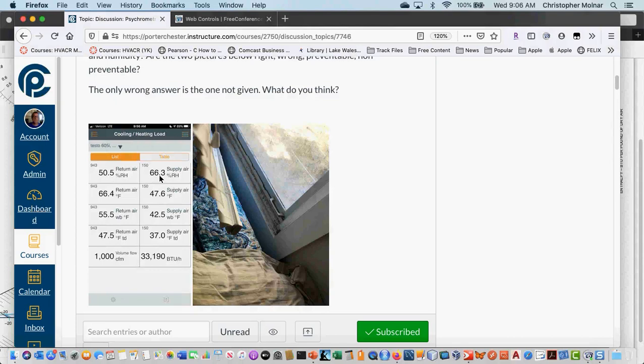I have a 66.3 relative humidity supply air. We talked about this yesterday, that the supply air can and should have a slightly higher relative humidity, but remember it has less grains of moisture. Remember that cooling process I did on yesterday's psychrometric chart. Return air is 66.4 degrees, supply air is 47.6.